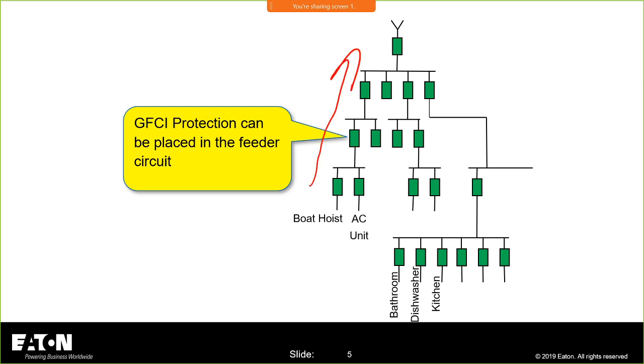...that you put ground fault, the more you have to worry about leakage currents. So 4 to 6 milliamps at this location may not be a good idea. Down here, probably not so much of a significant issue. You just got to think about all of these connected loads and any accumulated leakage currents that may cause you some tripping issues.